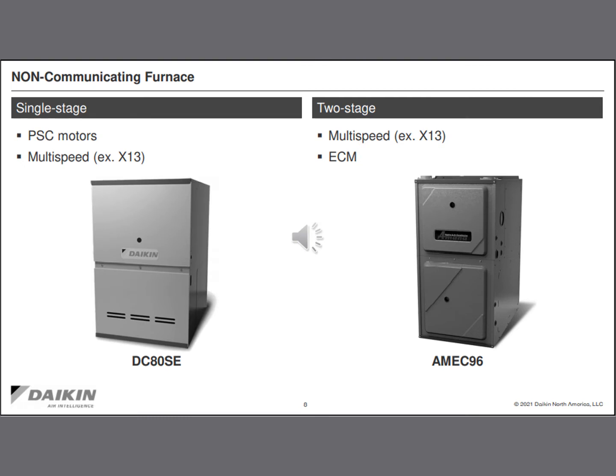So here are the compatible furnaces with this system. We can use a single stage furnace, either with a PSC blower or a multi-speed ECM blower, like an X13, or we can use a two-stage furnace that either has a multi-speed X13 or an ECM.